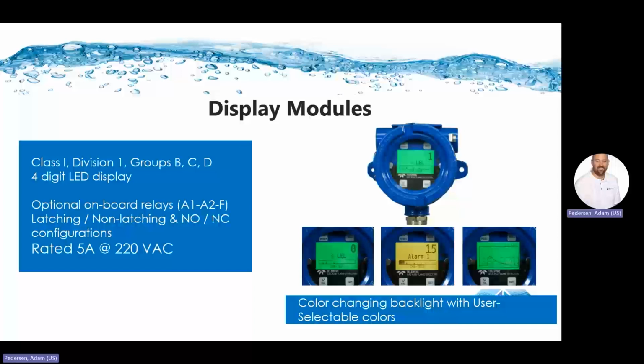Teledyne Gas and Flame Detection device here is a 4 to 20 milliamp output for this display module. The high resolution LCD display has 3 alternative display screens. The first screen shows the current measured concentration, target gas, and engineering units. The second screen also has a concentration bar graph with alarm set points, as well as an alphanumeric location ID. And on the third alternative screen, the display can show a trend graph of the most recent 30-minute history.